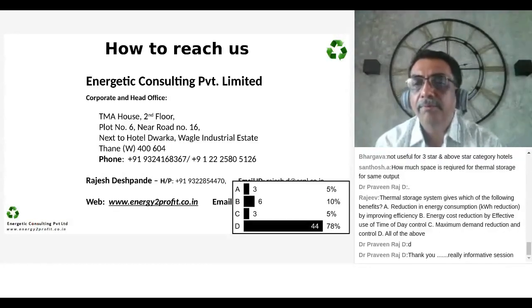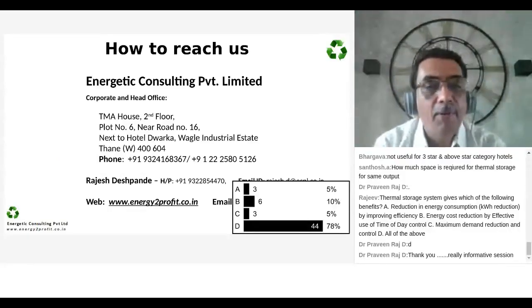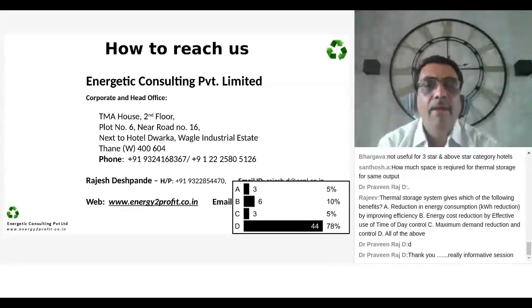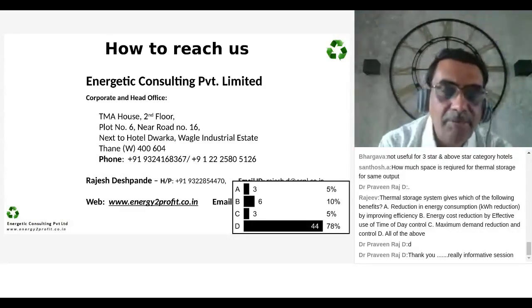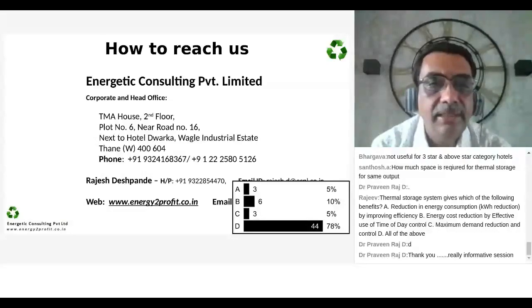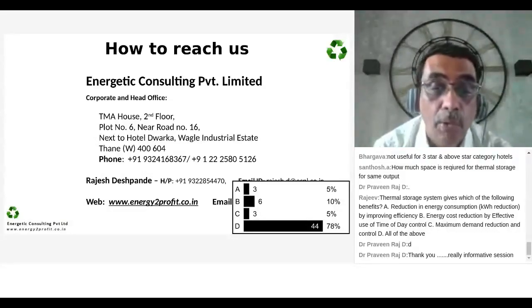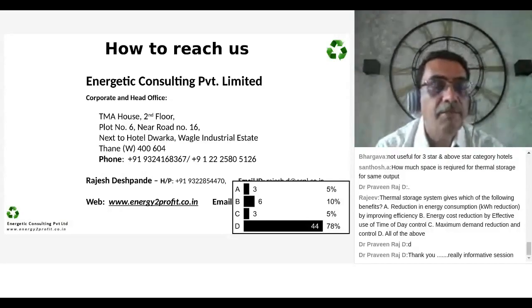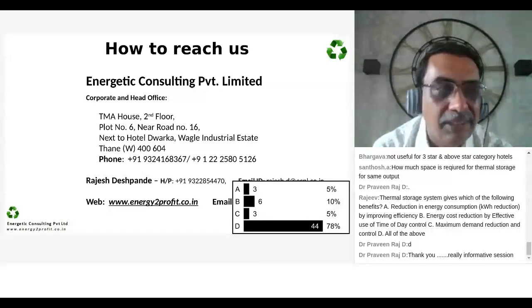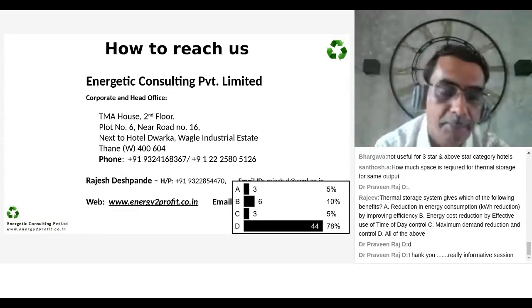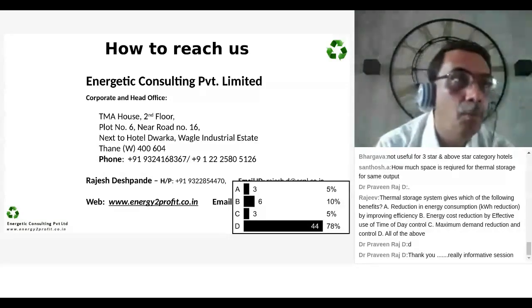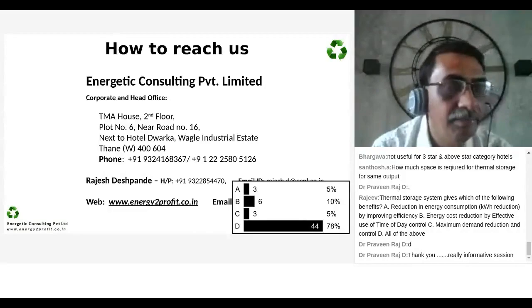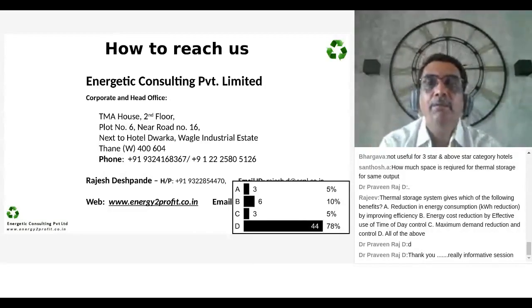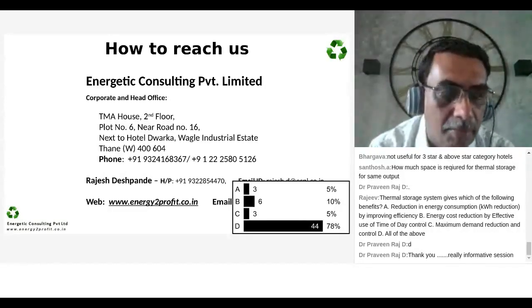Great. So 80% of the people have got it right, all of the above. Just a clarification once again: reduction in energy consumption is of the overall system. Compressor energy consumption does not reduce. In fact, the compressors operate more inefficiently, because they operate at a lower temperature. For the same TR output, they consume more energy. So this is not meant for reduction in compressor performance.